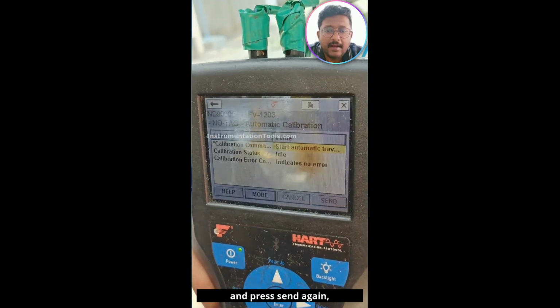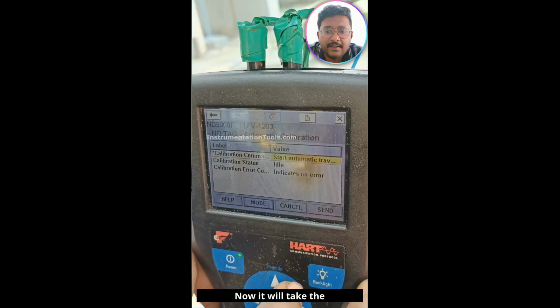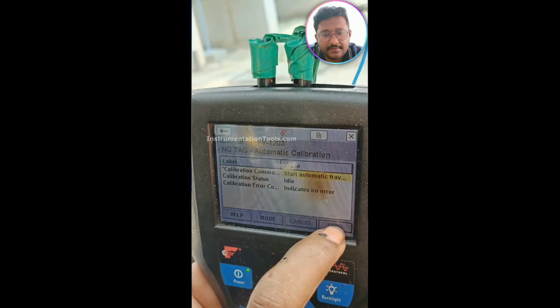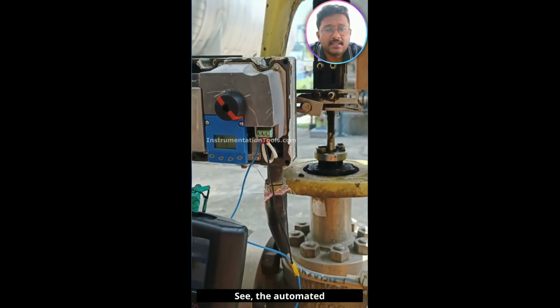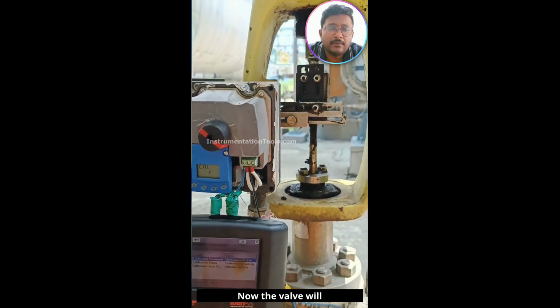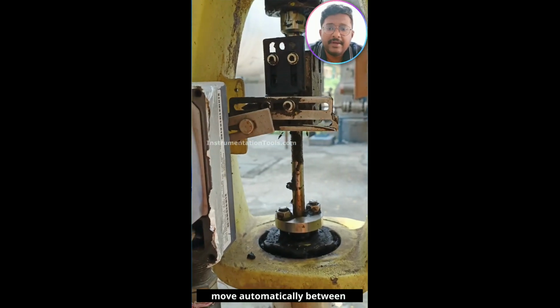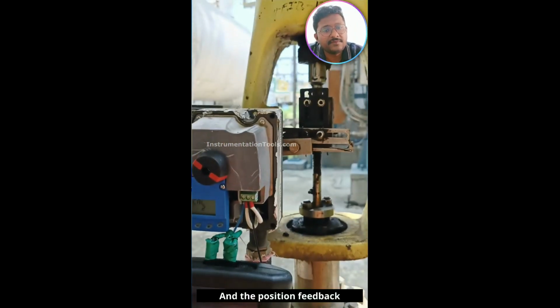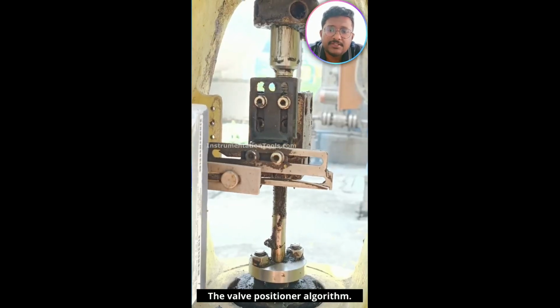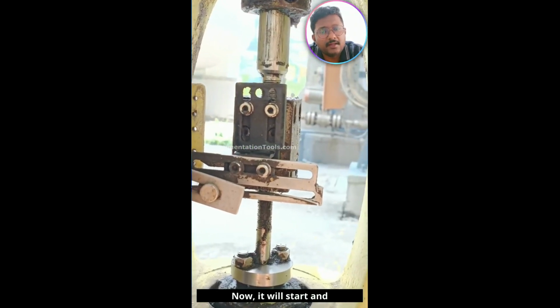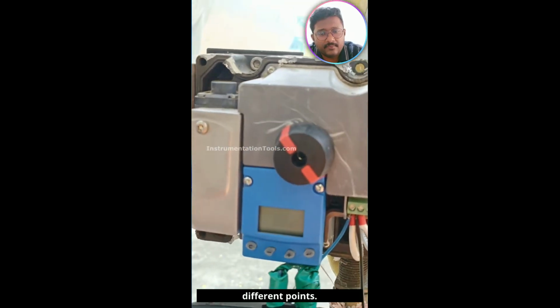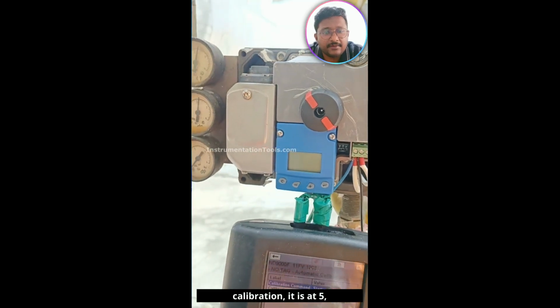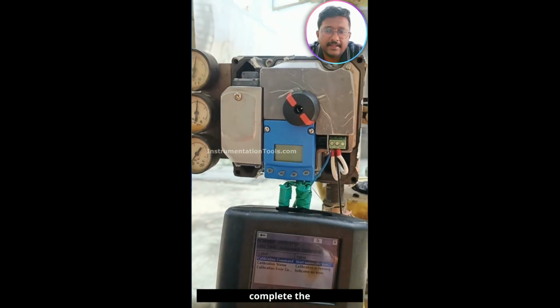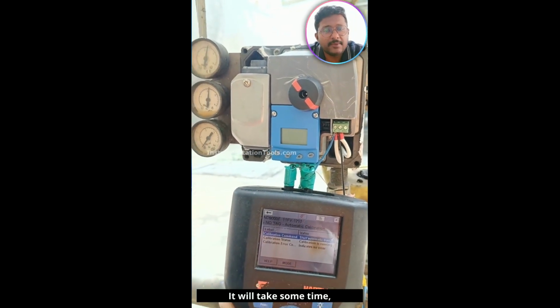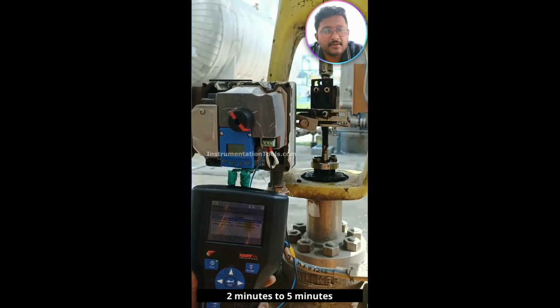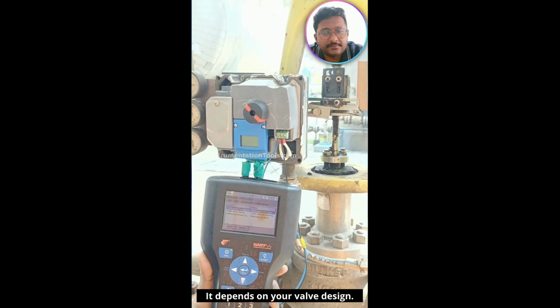Click yes and press send again, send button. Now it will take the command, calibration will be started. See, the automated travel calibration is started. Now the valve will move automatically between predefined stem positions, and the position feedback also adjusted. The valve positioner algorithm, now it will start and it will check for different points. See the cal means calibration. It is at 5. It has to reach 100 to complete the calibration. It will take some time, 2 minutes to 5 minutes.